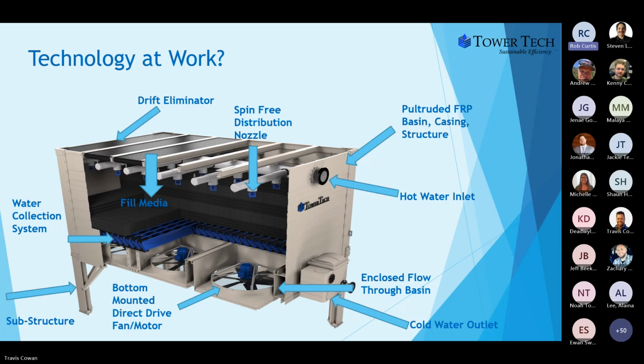So then the water goes on the perimeter basin and runs along the side of the cooling tower, and then it will hit a side mounted sump box here that you can see that has a lid on the top of it. Inside that sump box is your suction screen and your makeup valve and your equalization connection. What we're wanting to do is keep people outside of the cooling tower. Nobody wants to go in the cooling tower. And if you can develop a design that mitigates and minimizes going inside the cooling tower, you've truly made something safer and even more sustainable.